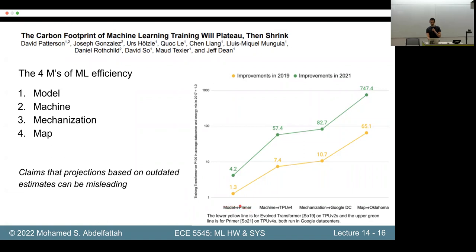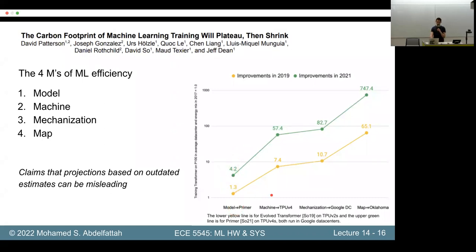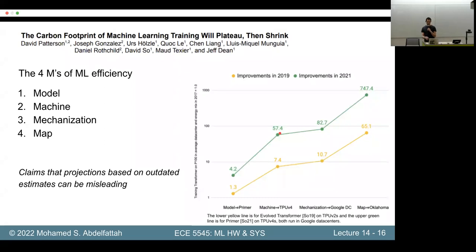Changing the machine — running on a TPU V4 instead of a P100 GPU — gives 7 to 57x improvement in energy, a very big margin. Then changing the mechanization: instead of running on a P100 in an average data center with a bad PUE of 1.6, run it on Google's data centers with a PUE of 1.1. Then you go to 10x or up to 80x improvement depending on the model.